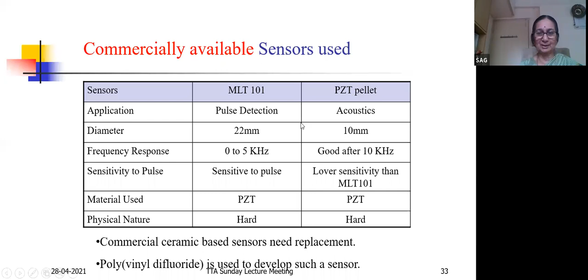Then we were having acoustic sensors, and the PZT pellet of it we removed. Its sensor was also 10 millimeter. Frequency response was beyond 10 kilohertz, whereas the frequency response required is from 0 hertz, because the human pulse is 1 to 1.2 hertz only. So we require a frequency response right from 0. The sensitivity was lower. It was again a PZT and hard. So we could not use this, and so we thought of developing our own sensor.